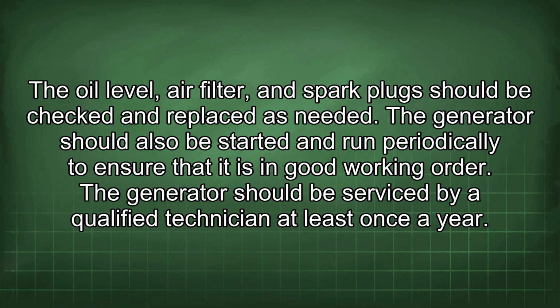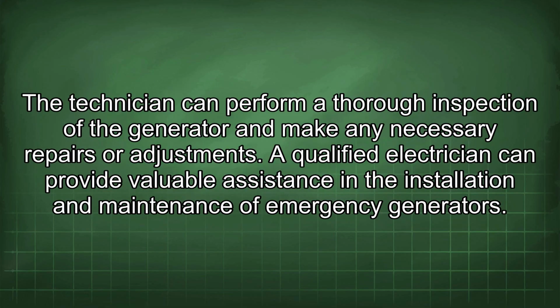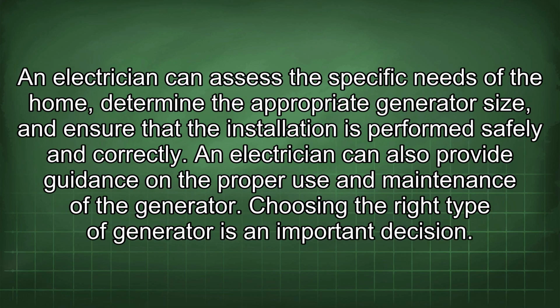A generator should be serviced by a qualified technician at least once a year. The technician can perform a thorough inspection of the generator and make any necessary repairs or adjustments. A qualified electrician can provide valuable assistance in the installation and maintenance of emergency generators. An electrician can assess the specific needs of the home, determine the appropriate generator size, and ensure that the installation is performed safely and correctly. An electrician can also provide guidance on the proper use and maintenance of the generator.